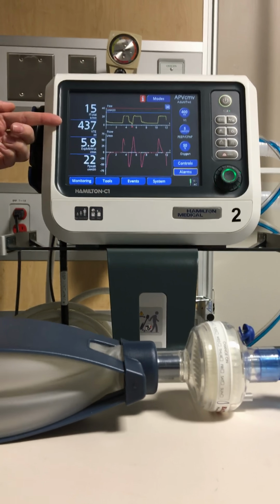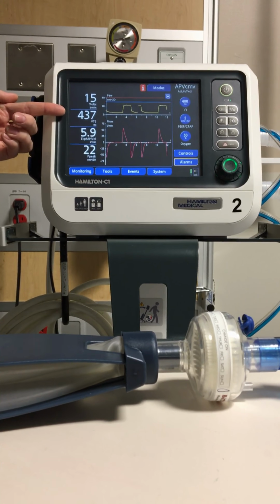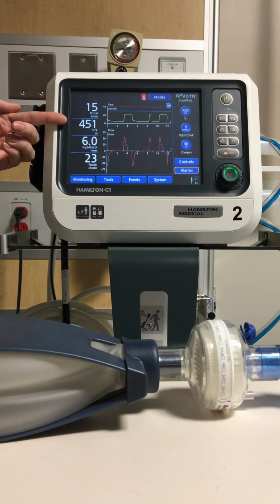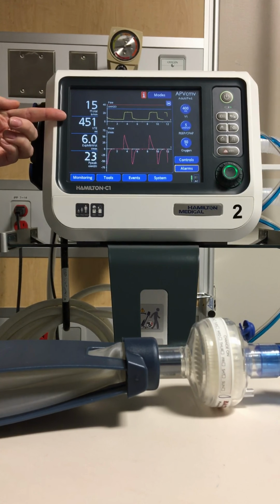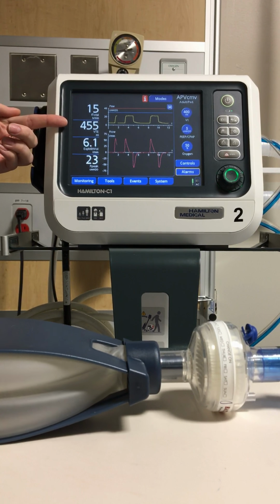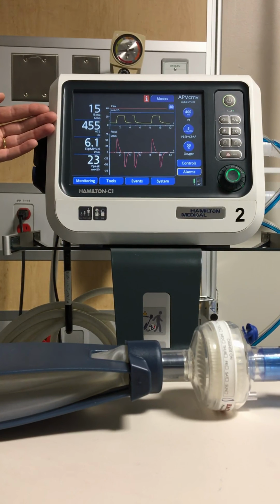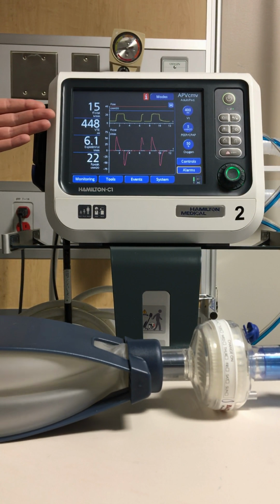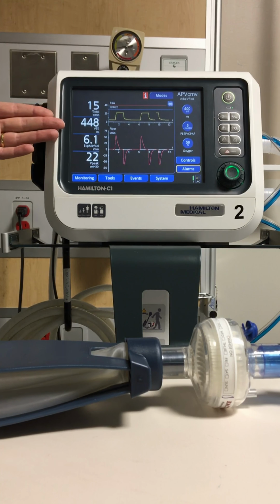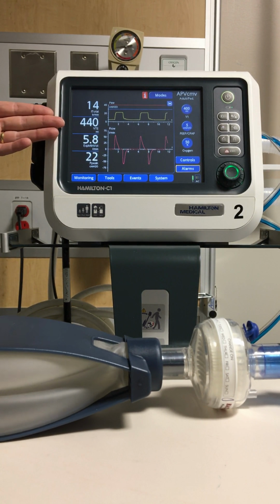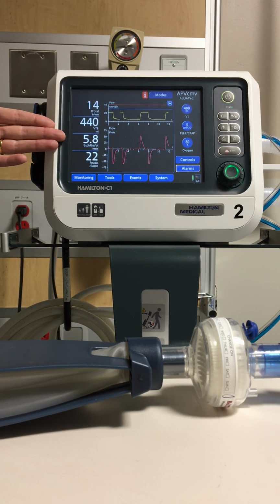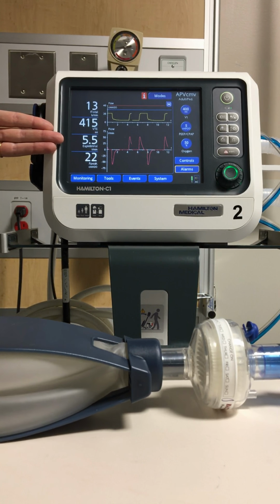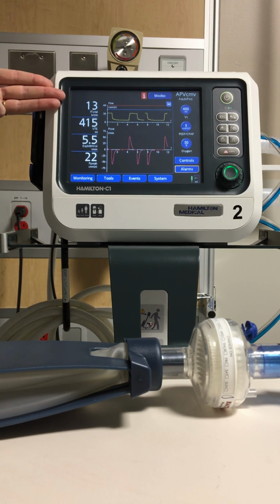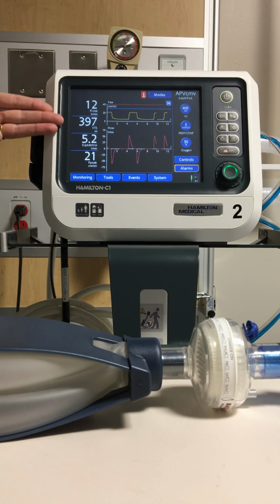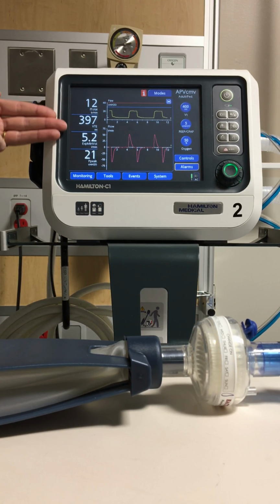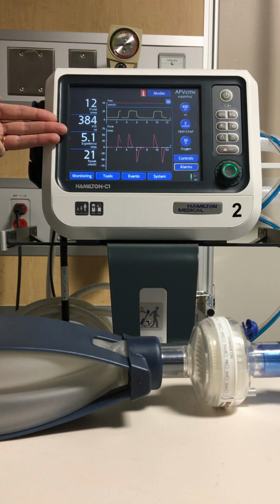The second value that we have monitored here is the volume. So this is the tidal volume, exhaled volume in milliliters. This is the volume that the ventilator is receiving back into it from the patient, sensed at the flow sensor. Therefore, we know what the patient is actually getting, and we can determine if there is a leak in the system or a cuff leak on the endotracheal tube. Next monitored value here is the expired minute volume. This is simply a multiplication of the respiratory rate that the patient is actually receiving and the volume that the patient is actually receiving to give us an expired minute volume.